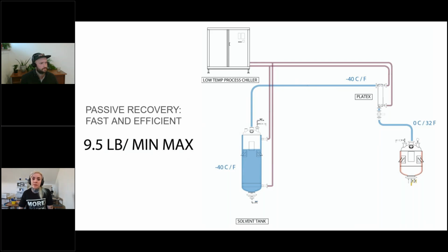It's relatively relaxed. Yeah, the safety can't be overstated, I think, because the way that a passive system functions requires an appropriate pressure differential. So the greater the difference between your evaporation pressure and the pressure in the vessel where you're recovering to, the faster you can go. And so along those lines, your control over your temperatures and your pressure is your recovery speed. And what's great about that from a safety perspective is that if you fail to generate enough pressure or you have too much back pressure in that receiving vessel, what will happen is nothing. Passive recovery will just stop. It will just equalize.